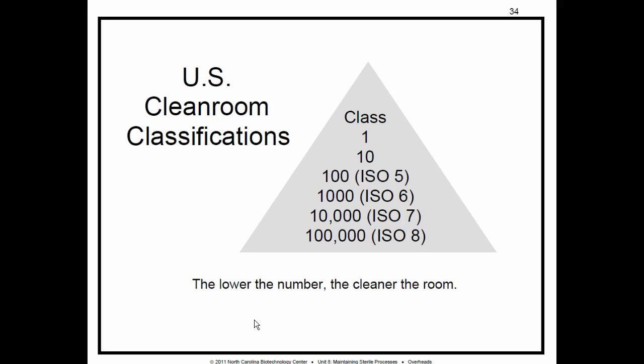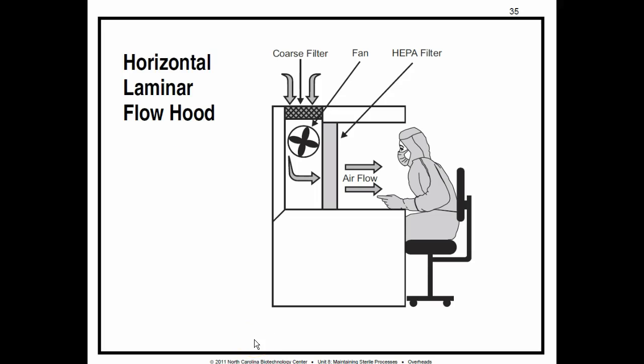On page 62, we're talking about clean workstations. Clean workstations are usually enclosed workbenches called laminar flow hoods, or cubicles partitioned off with plastic curtains. At these workstations, materials are protected from contamination by filtered laminar airflow. The workstations have their own HEPA filters — they're kind of like miniature clean rooms. For example, you may see Class 100 hoods or cubicles within Class 10,000 clean rooms.